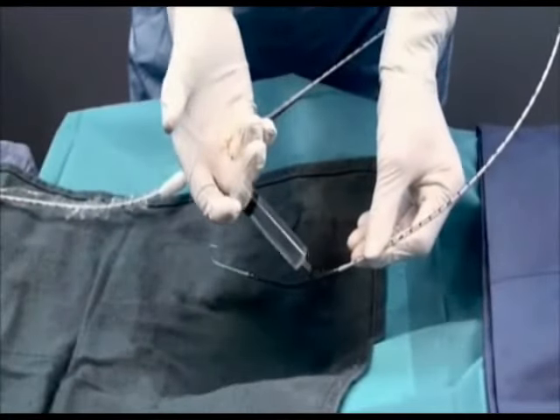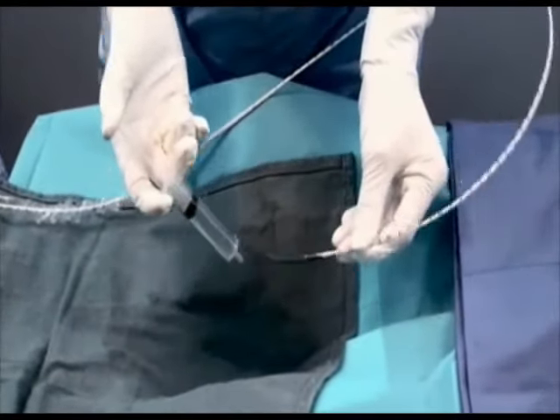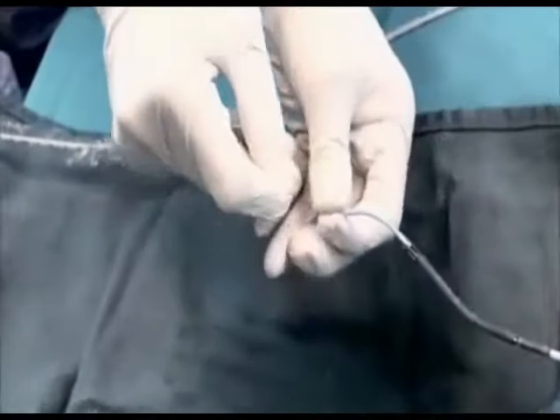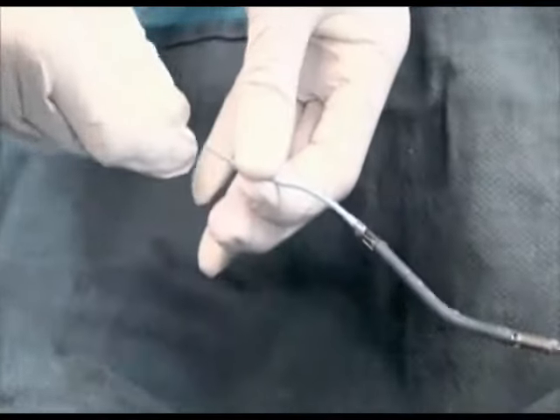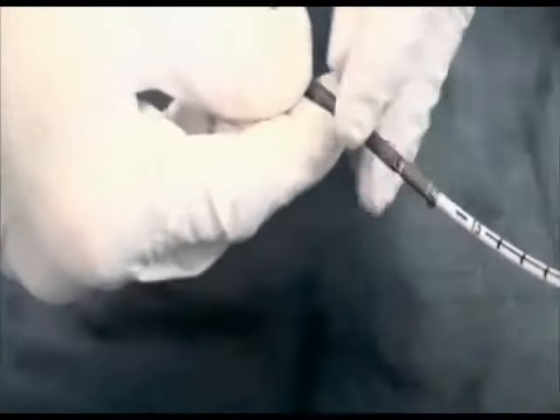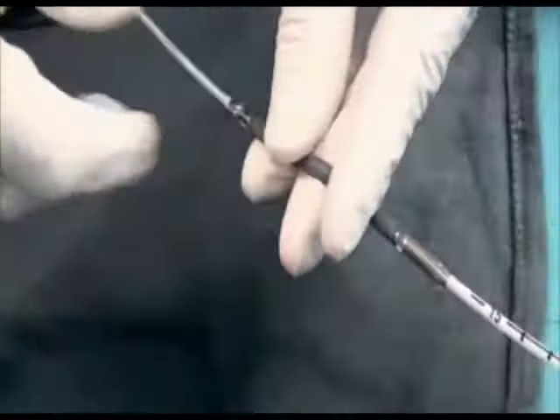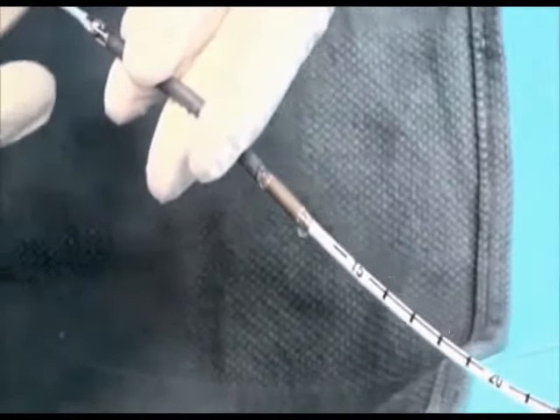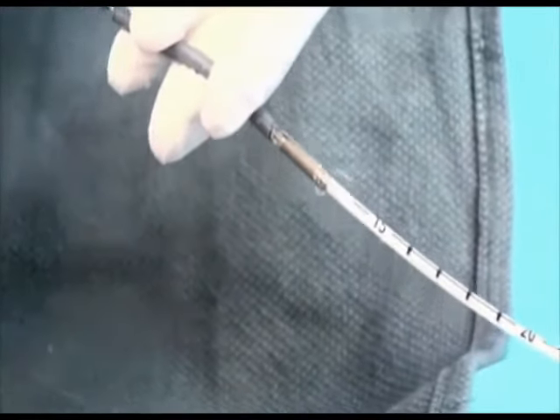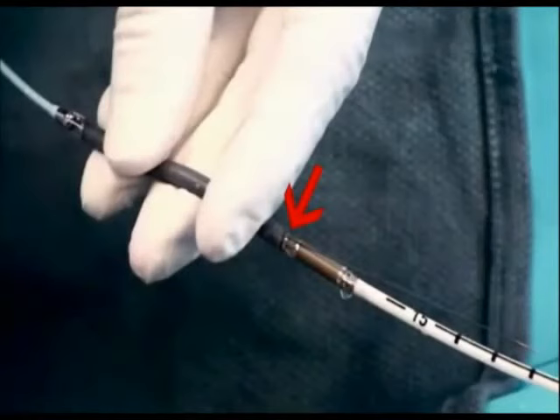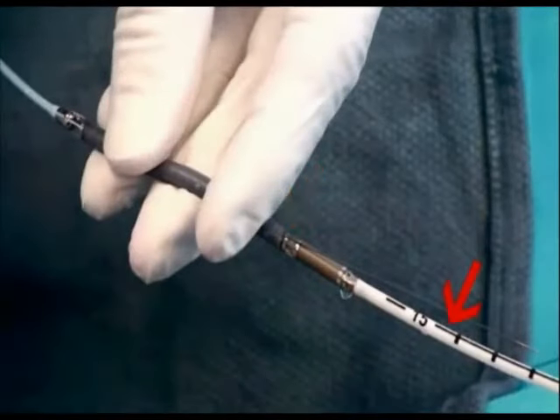Wet the cannula with sterile water and backload the pigtail section of the catheter onto the placement guide wire. Advance the guide wire into the Impella 2.5 catheter and stabilize the cannula between the fingers. This prevents pinching of the inlet area. The guide wire must exit the outlet area on the inner radius of the cannula and align with a straight black line on the catheter. The cannula can be hyperextended as necessary to ensure the guide wire exits on the inner radius of the cannula.